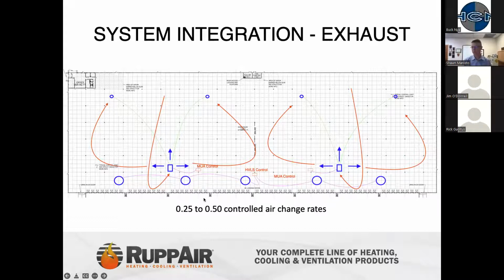And basically we're going to introduce air and pressurize the space and introduce air back to the exhaust fans in the back corner. Something to be aware of as well when you're doing your design layouts is where your north and west walls lay as well. They're normally the most common areas for condensation and buildup. So making sure you have good air movement across those north and west walls.